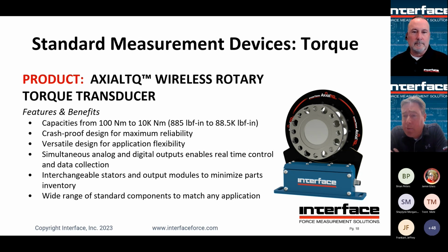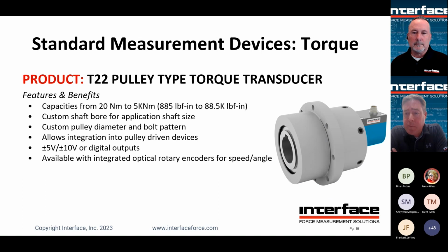A lot of different output types. These have frequency outputs, current outputs, and standard voltage outputs. You can actually take multiple outputs off of the output module. It's also designed to be interchangeable. So if you have a rotor that does get damaged, you can just swap the rotor out in real time, with no rescaling required for the output module. So it's just swap and go. We've got a wide range of different coupling types and different solutions for shaft integration on these as well. So, very good device.